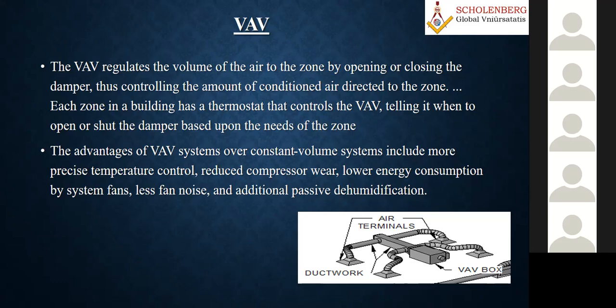The advantages of a VAV system over a constant volume system include more precise temperature control and reduced compressor wear. Because when you adjust it and a partial load condition happens, your return air and chilled water temperature, the delta T, also change. So accordingly, if you have a chilled water chiller with 6 compressors, there will be 3 in circuit A and 3 in circuit B. So there should be a logic in the chiller, a building logic.